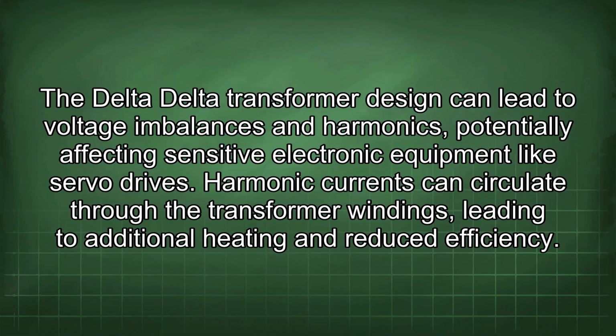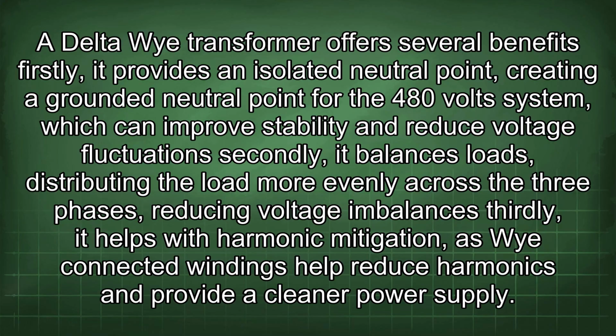Delta-Delta transformer design can lead to voltage imbalances and harmonics, potentially affecting sensitive electronic equipment like servo drives. Harmonic currents can circulate through the transformer windings, leading to additional heating and reduced efficiency. A Delta Wye transformer offers several benefits.